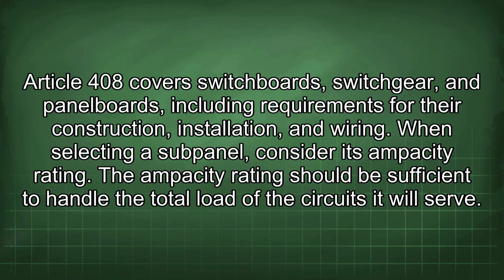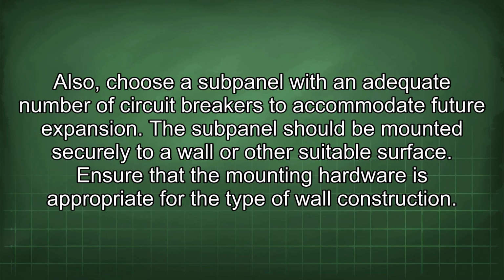When selecting a subpanel, consider its ampacity rating. The ampacity rating should be sufficient to handle the total load of the circuits it will serve. Also, choose a subpanel with an adequate number of circuit breakers to accommodate future expansion. The subpanel should be mounted securely to a wall or other suitable surface. Ensure that the mounting hardware is appropriate for the type of wall construction.